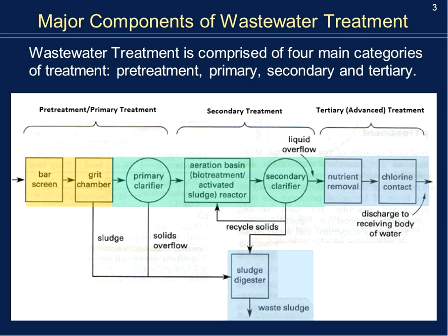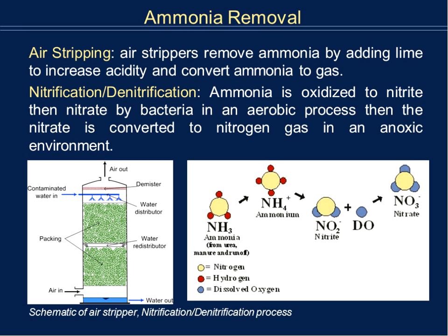Now that we've talked about clarification in advanced treatment and nutrient removal, we're going to talk about chlorine and disinfection. We mentioned the concept of air stripping: we use air to either decrease or increase acidity, and to convert different types of liquids or gases into other forms. One particular example is to convert ammonia into gas. Air comes in, the influent comes in, air is forced up through different types of media filters, and the reaction of air and water — aeration — causes the ammonia to convert to gas.